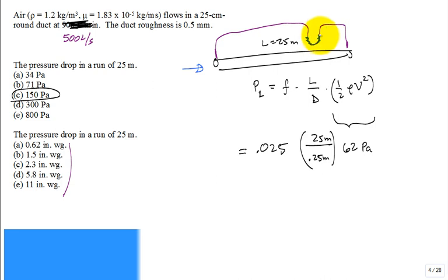So it'll shift to the right. This goes down a little bit. And now we have a little difference in the height. And that's how they describe that pressure. Inches of water gauge, the height difference between the two sides in that water manometer. So we recall the pressure loss we just calculated, around 150, I think it's 155, 154 Pascal.